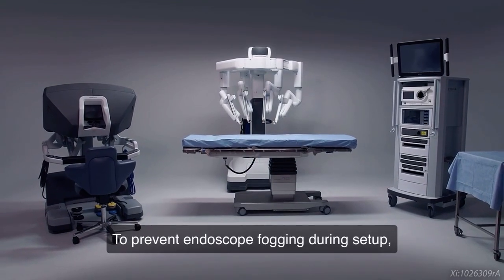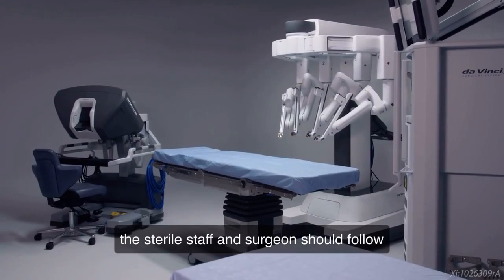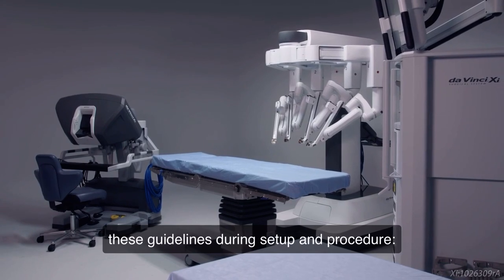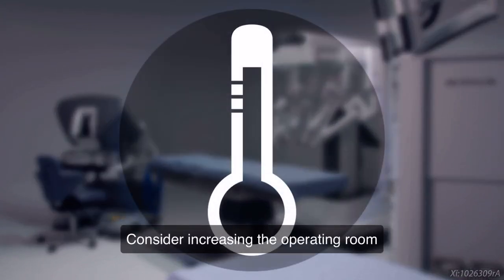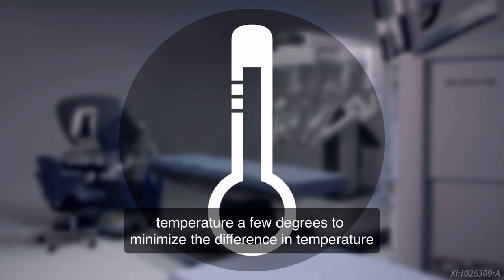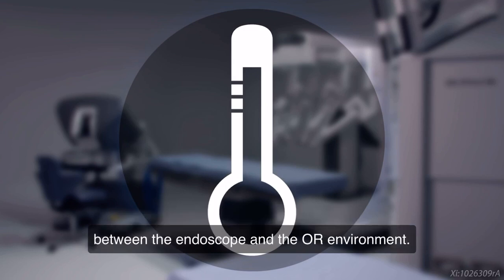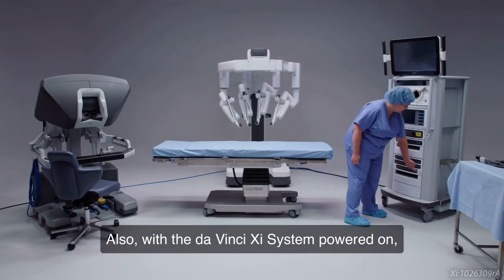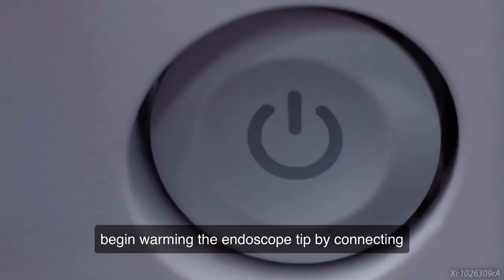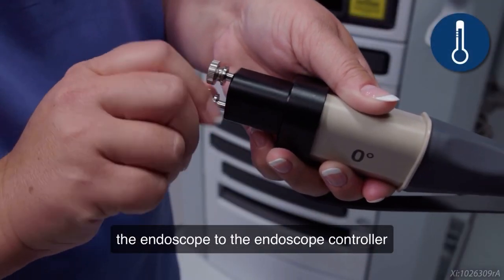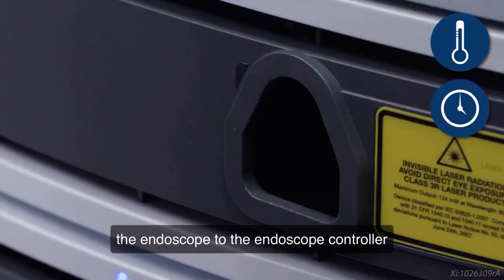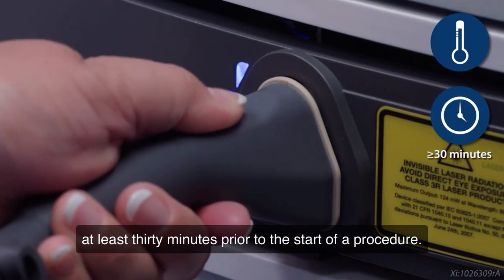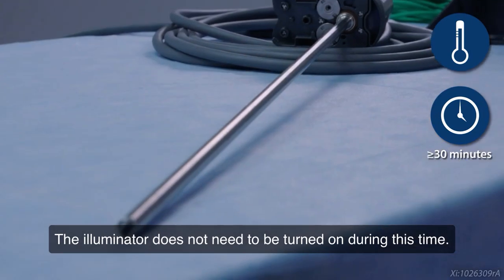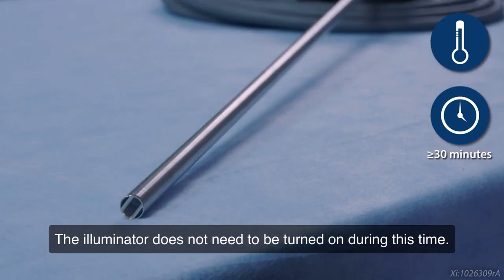To prevent endoscope fogging during setup, the sterile staff and surgeon should follow these guidelines during setup and procedure. Consider increasing the operating room temperature a few degrees to minimize the difference in temperature between the endoscope and the OR environment. Also, with the da Vinci Xi system powered on, begin warming the endoscope tip by connecting the endoscope to the endoscope controller at least 30 minutes prior to the start of a procedure. The illuminator does not need to be turned on during this time.